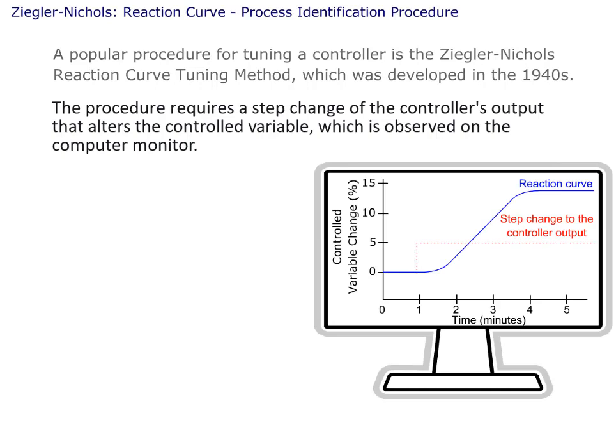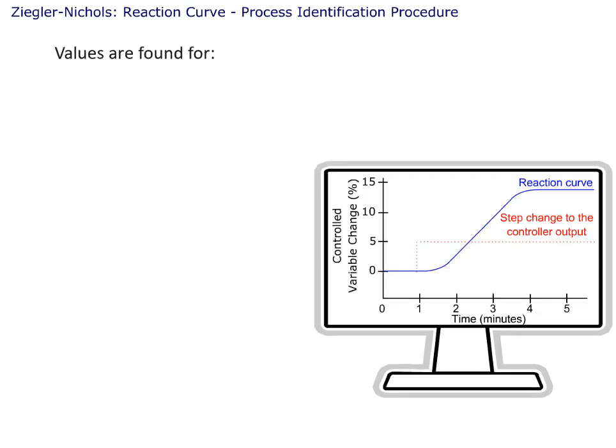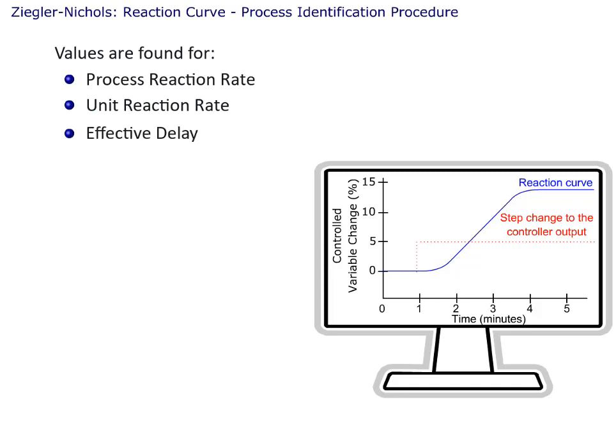The procedure requires a step change of the controller's output that alters the controlled variable, which is observed on the computer monitor. Based on the shape and magnitude of the controlled variable's reaction curve in reference to the step changes, values are obtained and used in mathematical formulas. Values are found for the process reaction rate, the unit reaction rate, and the effective delay.